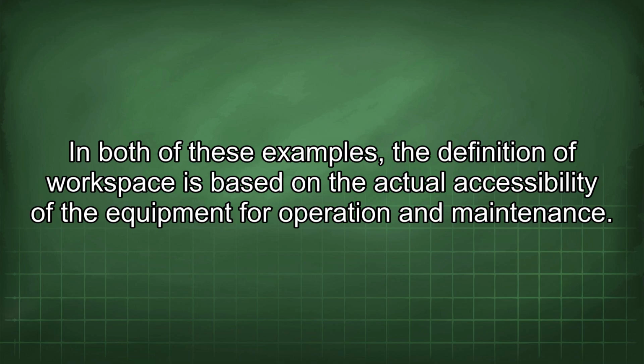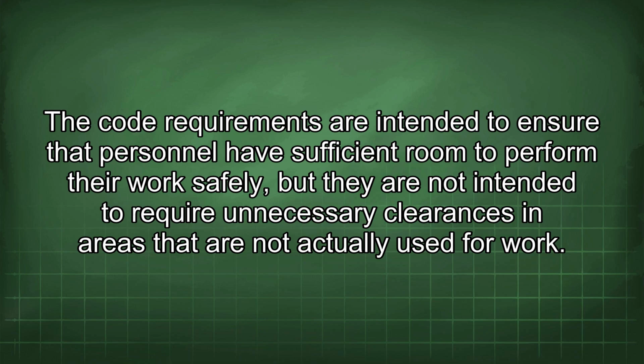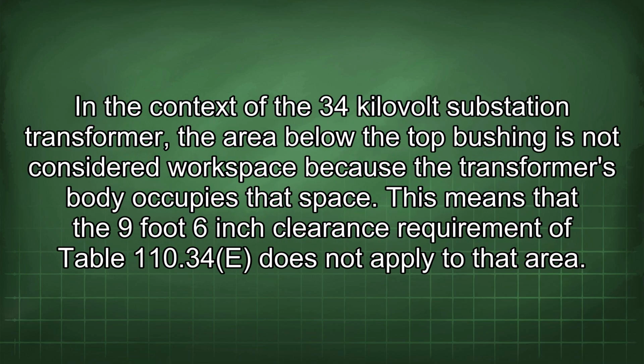In both of these examples, the definition of workspace is based on the actual accessibility of the equipment for operation and maintenance. The code requirements are intended to ensure that personnel have sufficient room to perform their work safely, but they are not intended to require unnecessary clearances in areas that are not actually used for work. In the context of the 34 kV substation transformer, the area below the top bushing is not considered workspace because the transformer's body occupies that space. This means that the 9 foot 6 inch clearance requirement of Table 110.34(E) does not apply to that area.